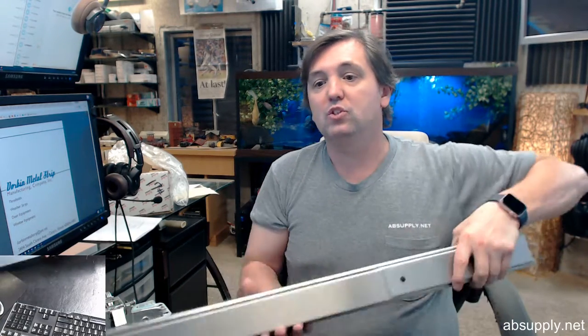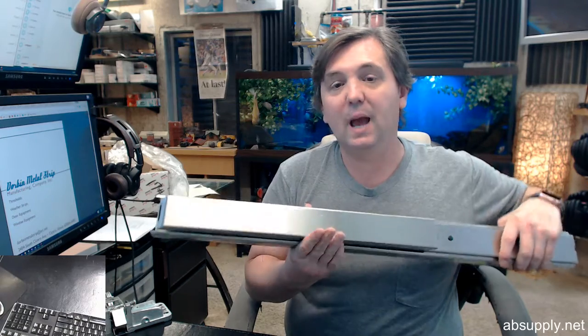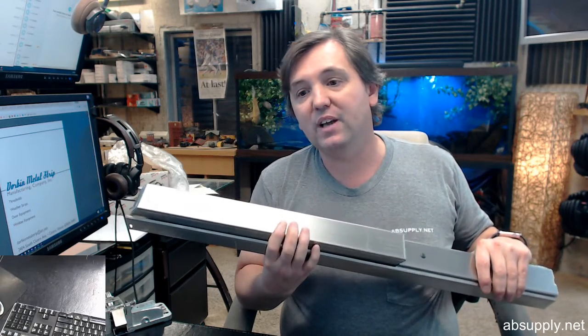Grade 1, that's meant it's tested to 1 million cycles. UL and CUL rated for up to 3-hour applications. UL 10D, UL 10C. California code, Title 19 compliant as well. The mortise devices are going to have the Dorma ML 9000 series, which are, of course, grade 1 rated as well. Handicap accessible, which is very important, the ability to get a handicap compliant device as well.